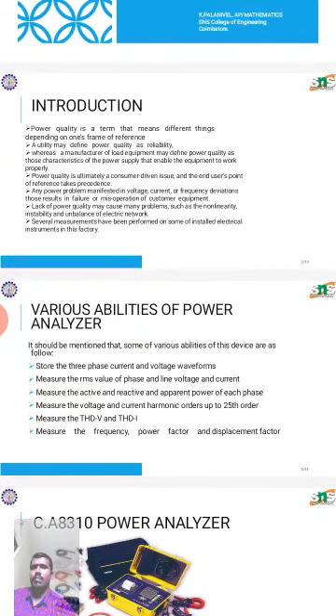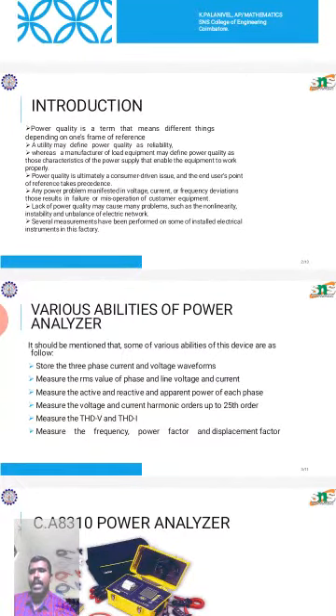Lack of power quality may cause many problems such as non-linearity, instability and unbalance of the electric network. Understanding power quality issues is a good starting point for solving any harmonic or complex problems. The significant reason that electrical engineers, and mechanical engineers also, are interested in power quality is economic value. There are economic impacts on utilities, their customers and suppliers of load equipment.